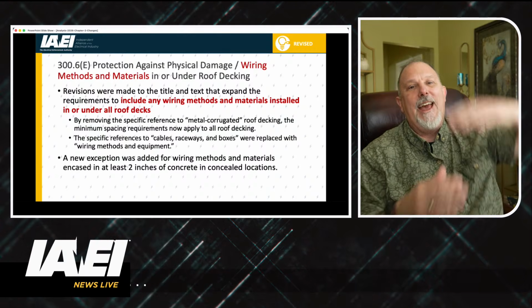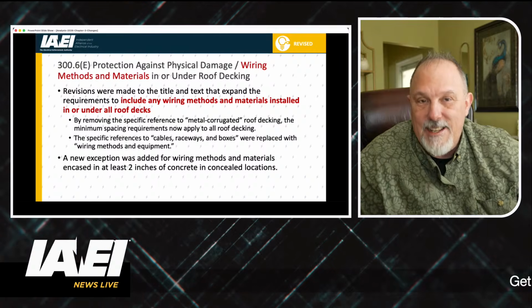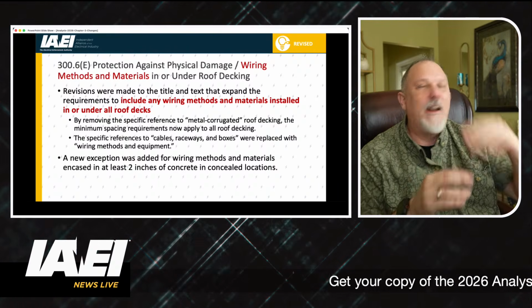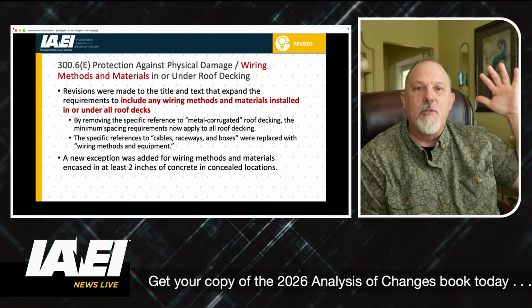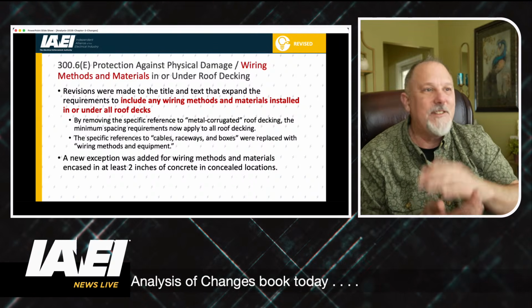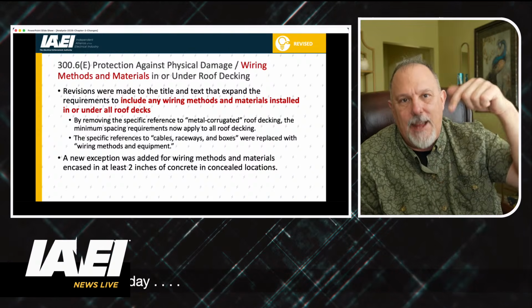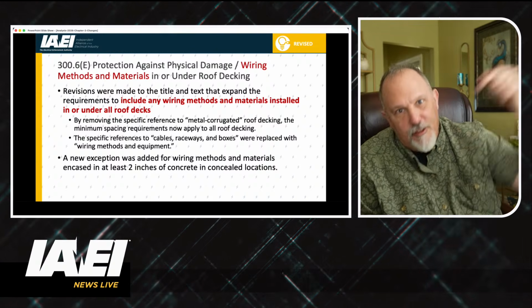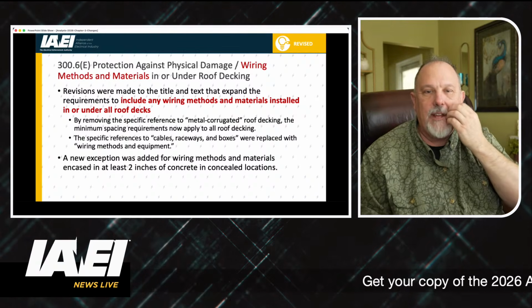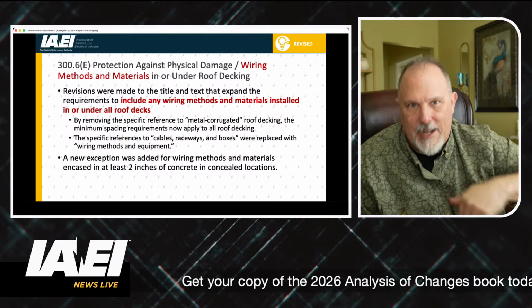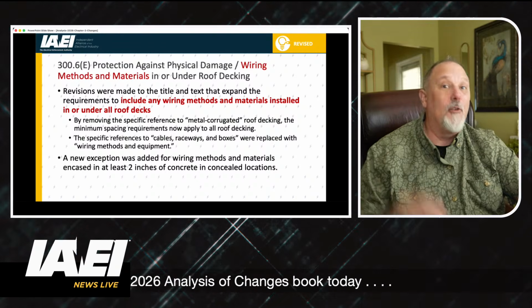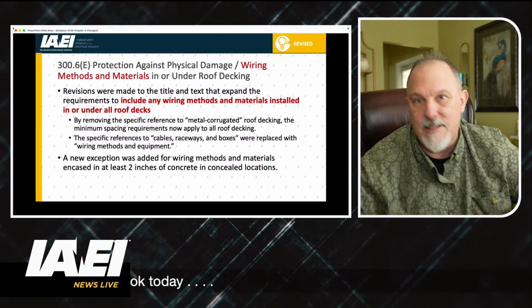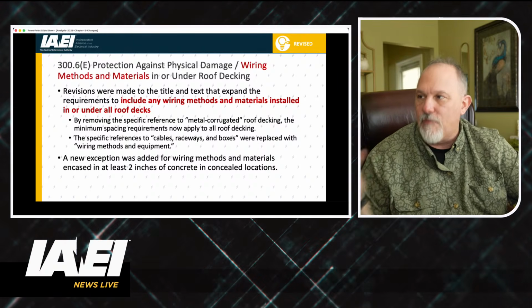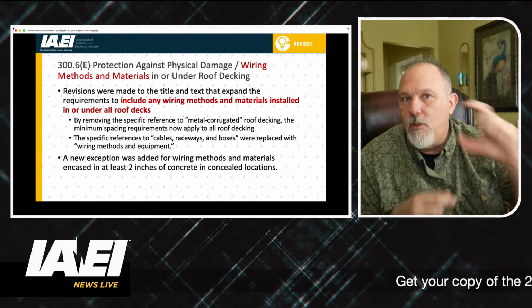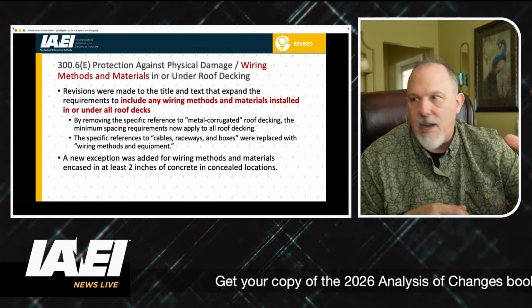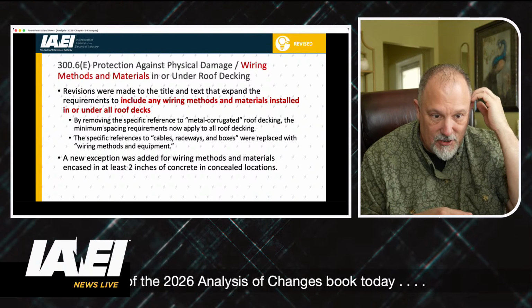And then they had to also say, all right, if I put a corrugated metal roof up and then I pour cement on top of it, there's no way that I'm going to drive an anchor through the concrete and through the corrugated steel and into your metal raceway or plastic raceway or whatever wiring method it is. So they also addressed that if you have at least 2 inches of concrete poured on top of that, I wonder if they used concrete.